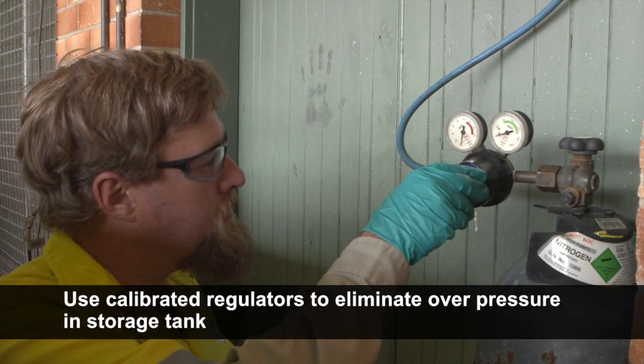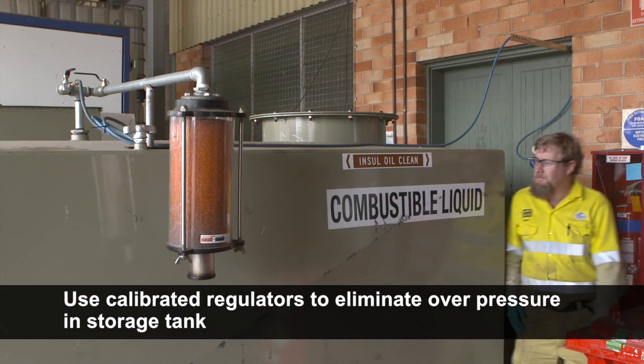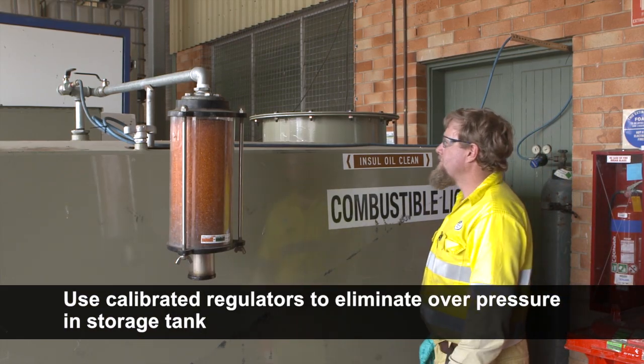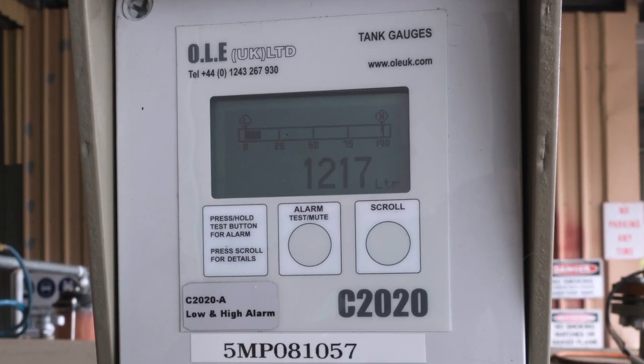If we can maintain or get oil at a high quality, probably the best thing we can do is put a blanket of nitrogen over the oil. Nitrogen equals no moisture. That means if we can get our oil at a high level, put a nice blanket of nitrogen over there, we should be able to maintain that oil at that really high level for extended periods of time.